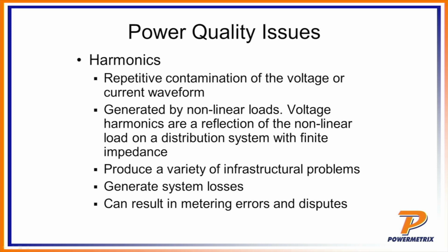Harmonics really are mostly generated by nonlinear loads. A nonlinear load basically means that if I take a load and I put it on a sinusoidal voltage source, I'm going to end up getting a response out of my system that no longer looks sinusoidal. It'll be periodic, it'll have the same waveform over and over again, but basically it'll no longer have a sine wave output. If I think about the current being a function of the load, if I apply a linear load to a sinusoidal voltage, I'll expect to get a sinusoidal current out of it. If I apply a nonlinear load to a sinusoidal voltage, I'll get a waveform out that looks nothing at all like a sine wave. And we'll see a couple examples here in just a second.